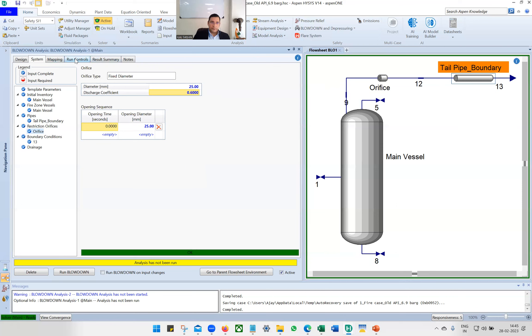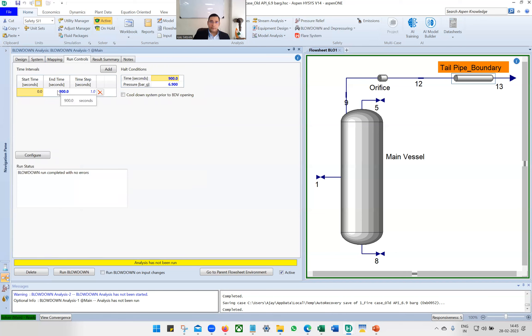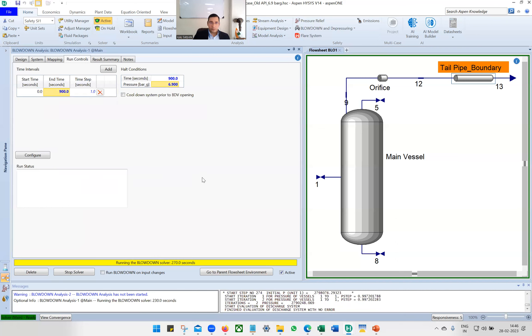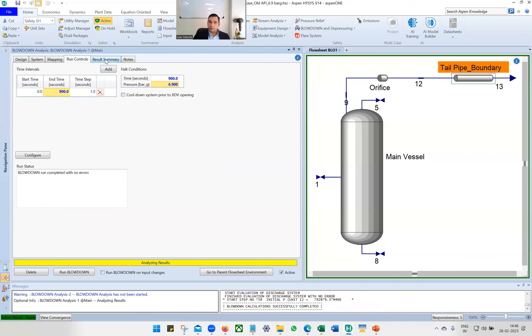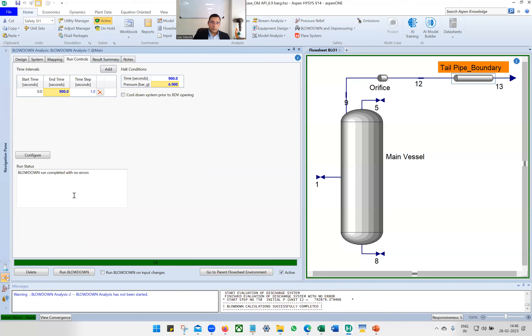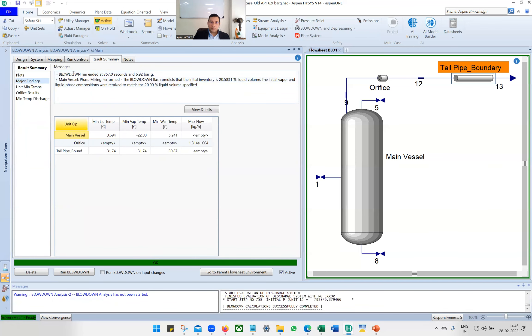Go to Run Control. As per the 50%/15 minutes rule, the time is 900 seconds (15 minutes) and the final pressure is 6.9 bar gauge. The simulation will halt when either of these criteria is satisfied. Once you click Run Blowdown, the result says blowdown run completed without any error. The blowdown run ended at 757 seconds and the final pressure was 6.92 bar gauge — very close to 6.9.